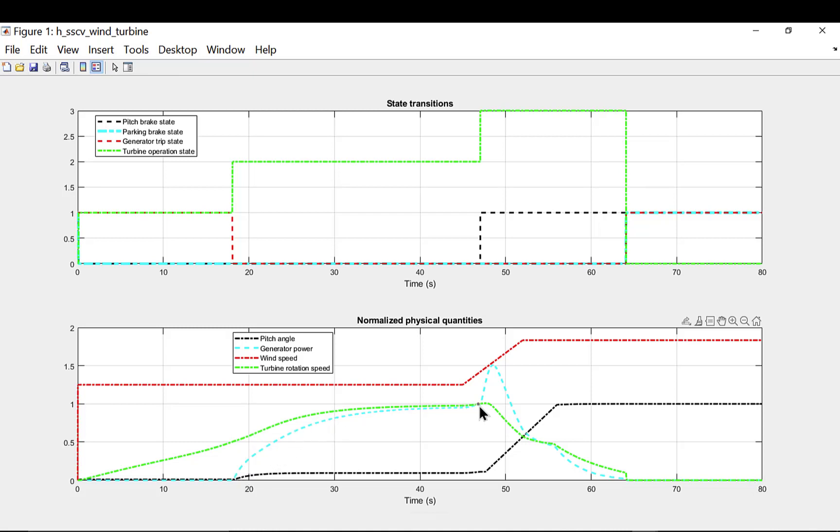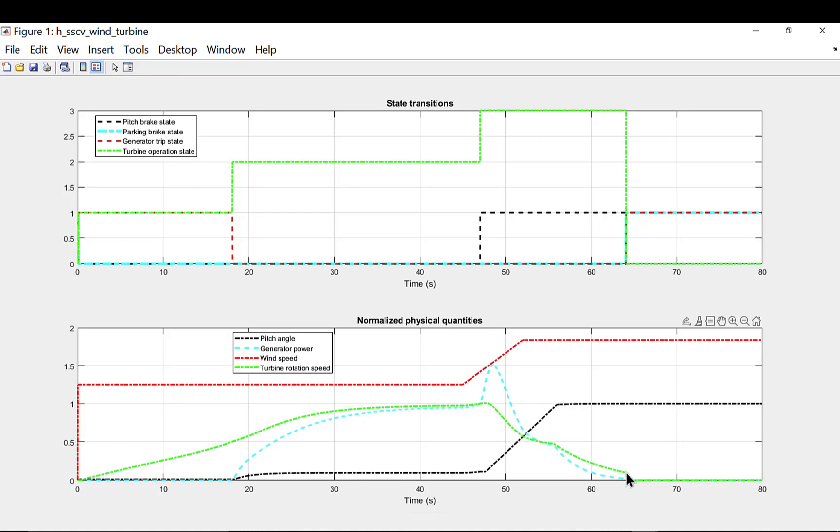When the wind turbine rotation speed or the wind speed goes above the cut-out speed, turbine enters the pitch brake mode. Pitch angle increases up to its maximum value and turbine decelerates up to park brake speed. Once it hits park brake speed, park brake mode gets active and hydraulic brakes are applied to the rotor and rotor comes to halt.